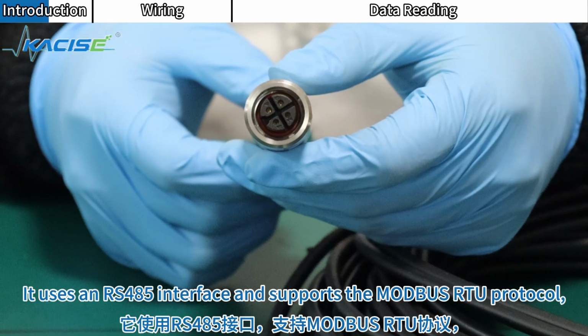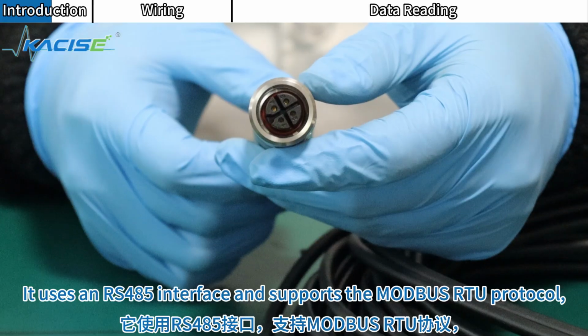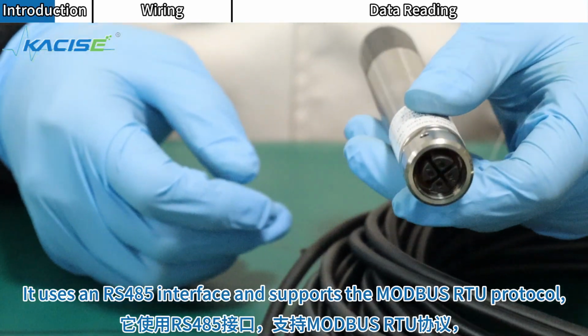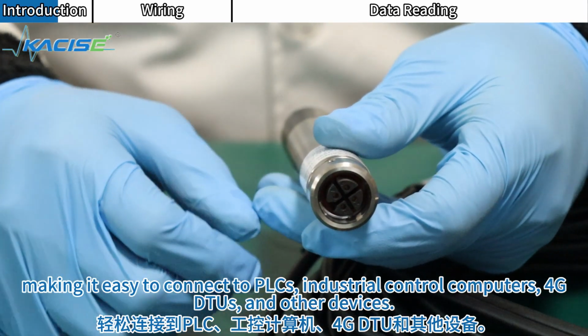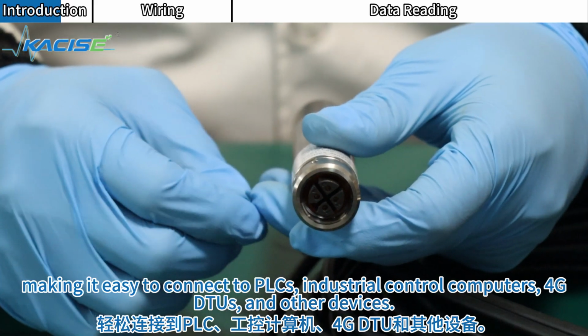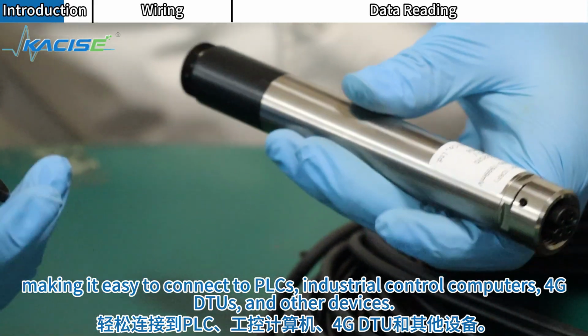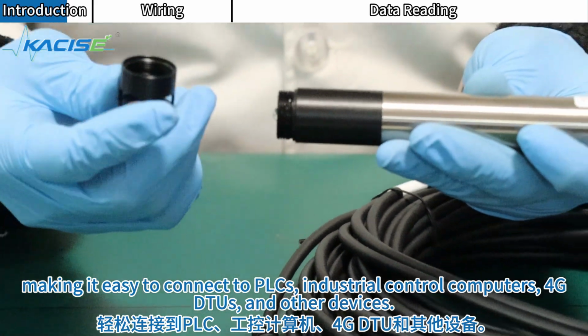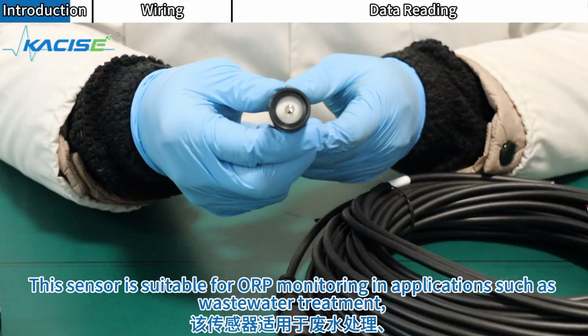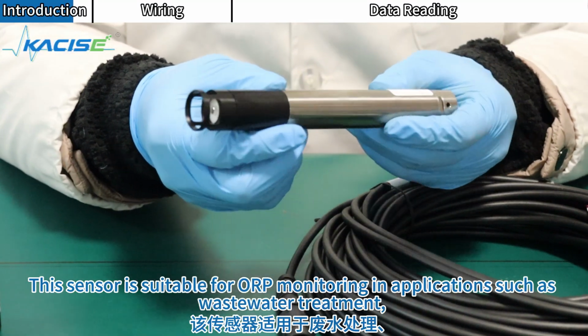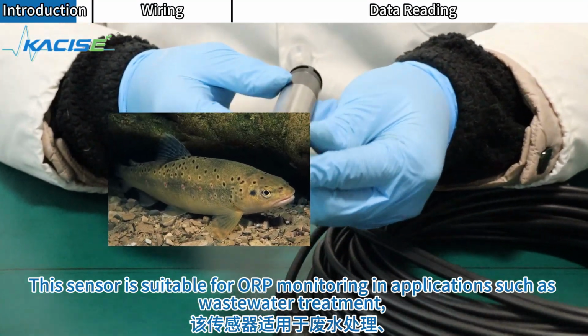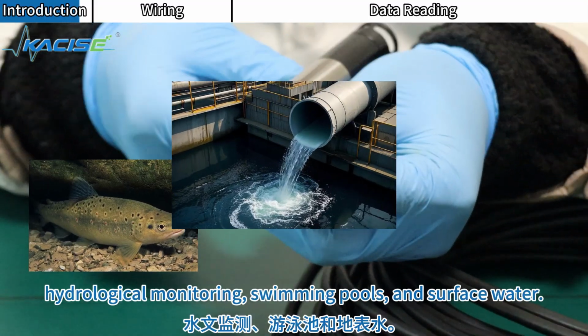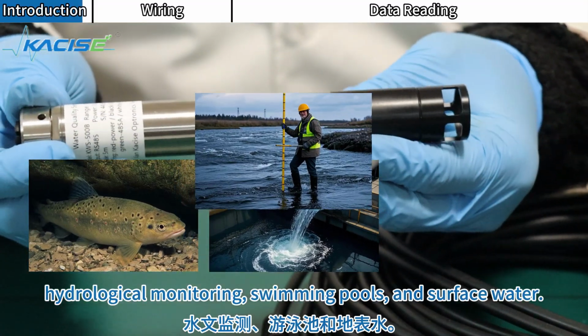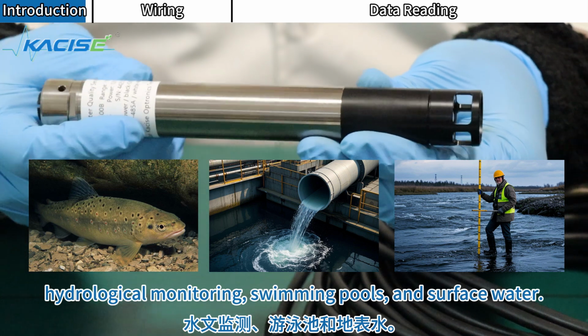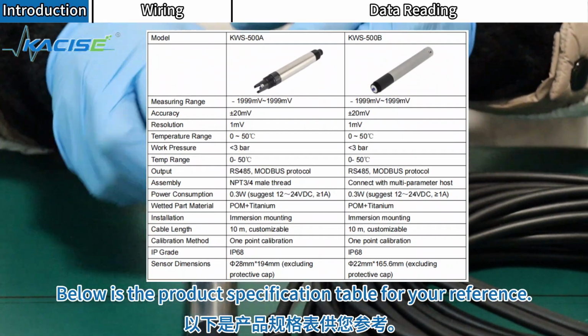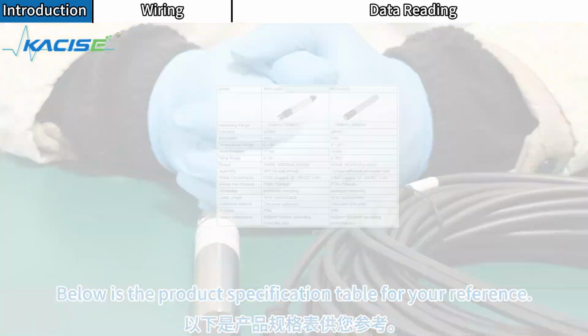It uses an RS-485 interface and supports the Modbus RTU protocol, making it easy to connect to PLCs, industrial control computers, 4G DTUs, and other devices. This sensor is suitable for ORP monitoring in applications such as wastewater treatment, hydrological monitoring, swimming pools, and surface water. Below is the product specification table for your reference.